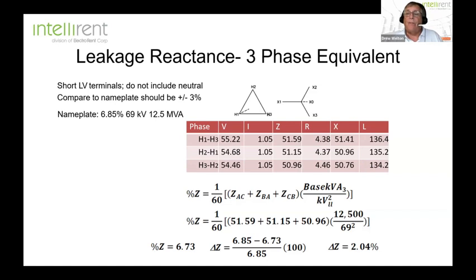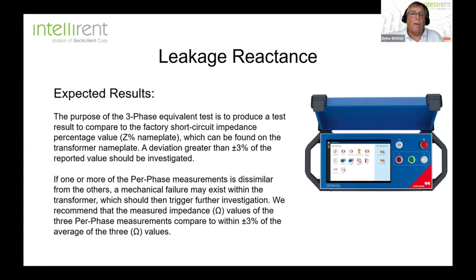And you can see here, this is a normal calculation of how we get the three-phase equivalent. And again, comparing that to the nameplate impedance measurement. And this, again, is your expected results. That three-phase equivalent should be plus or minus 3% of the nameplate, and per phase should be within 3% of the other values, the other phases.